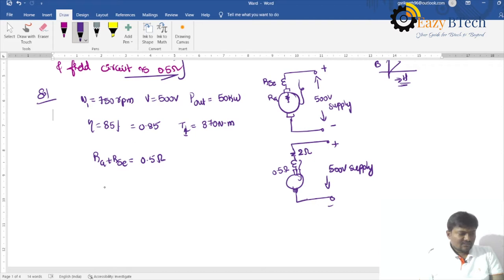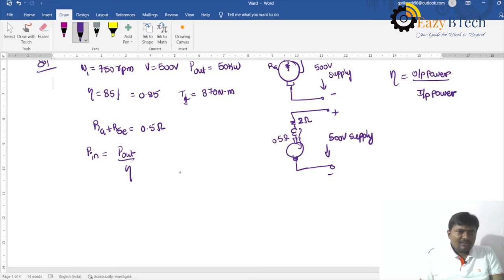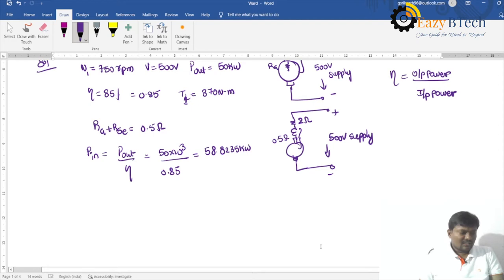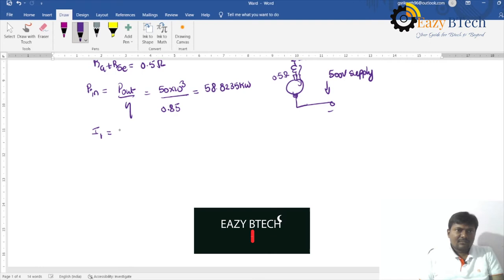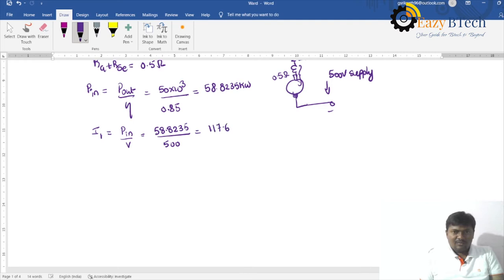To calculate the input power: efficiency equals output power divided by input power, so input power equals output power divided by efficiency. That is 50 × 10³ divided by 0.85, giving 58.8235 kilowatts. The current I1 equals input power divided by supply voltage: 58.8235 × 10³ divided by 500 equals 117.647 amperes.